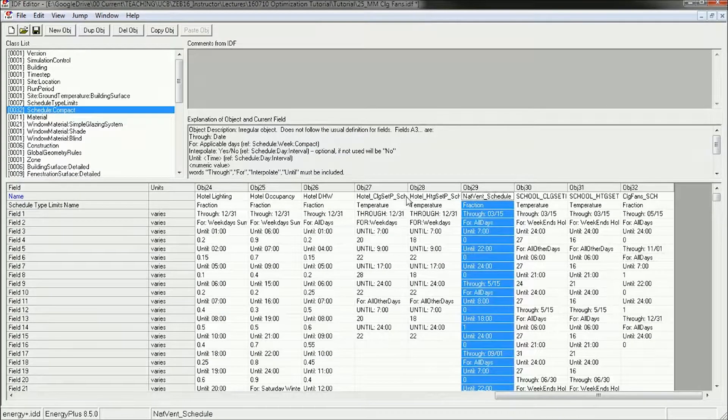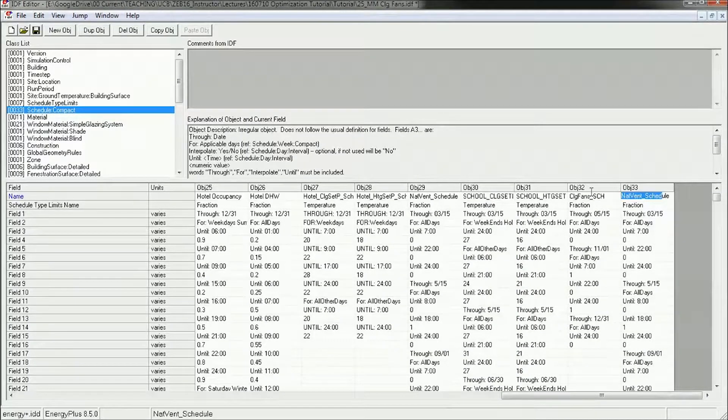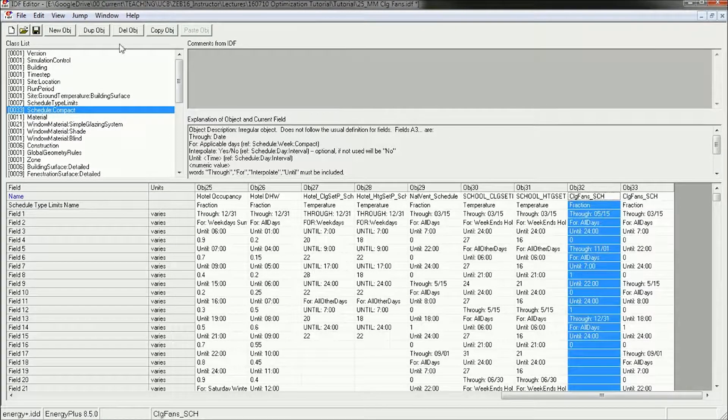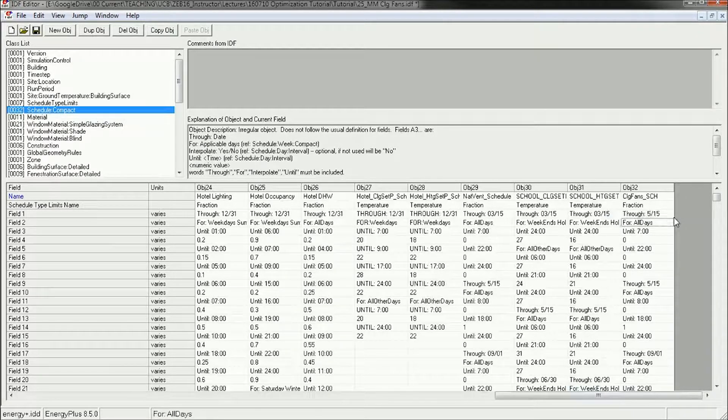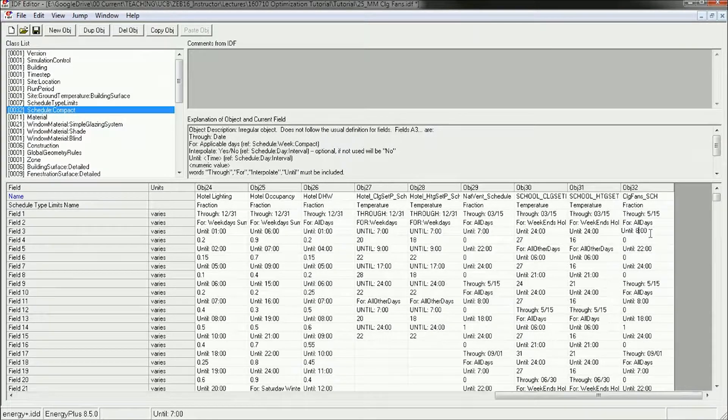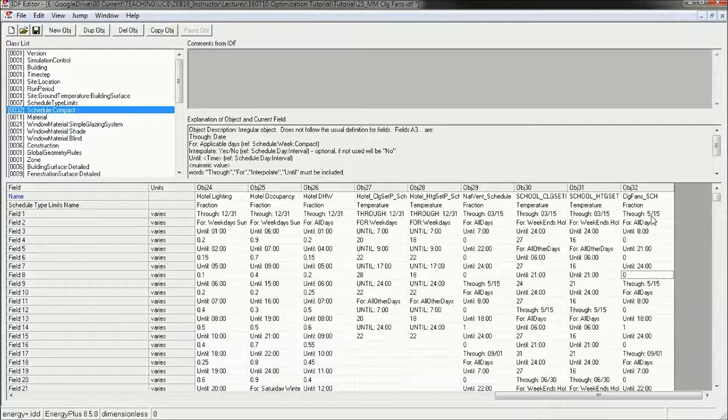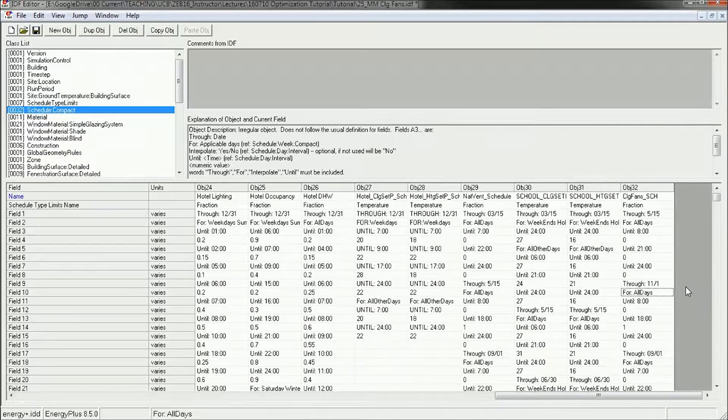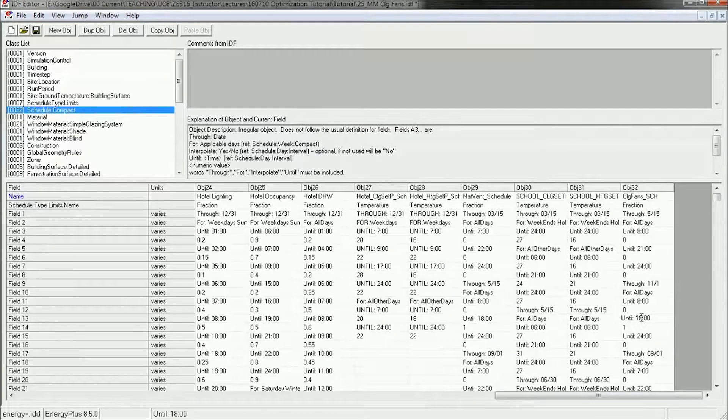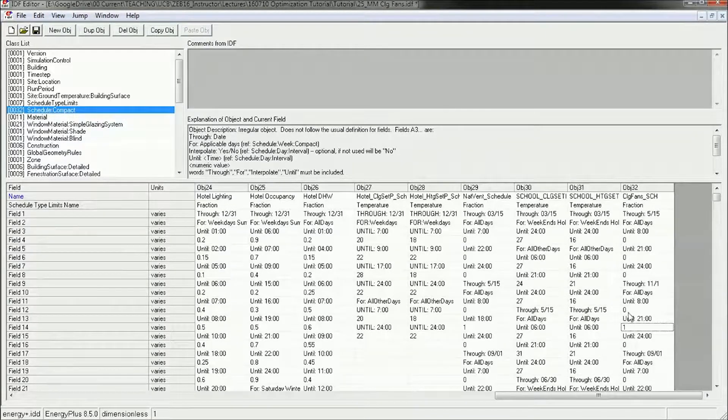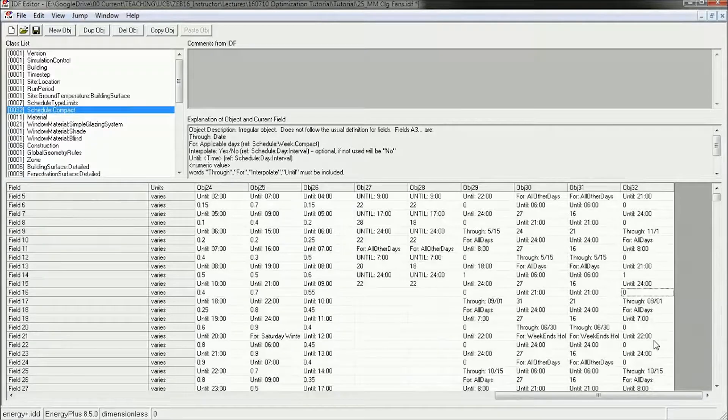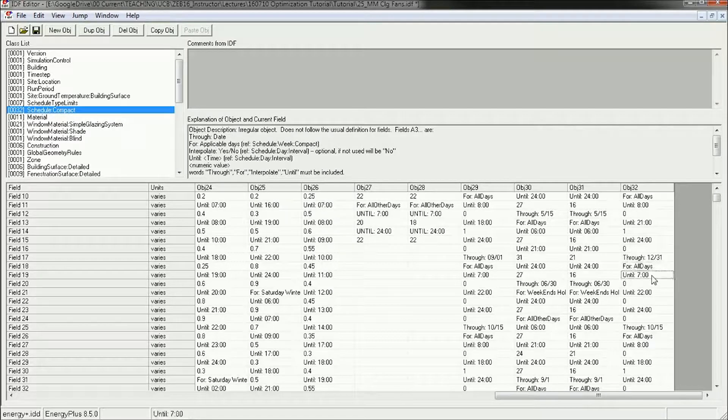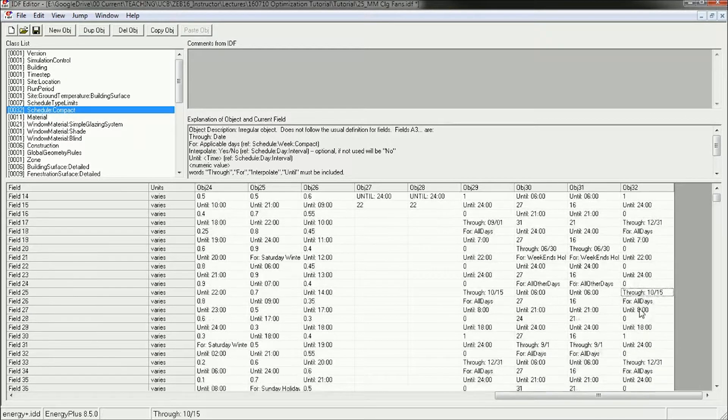Let's make... I'm going to use the natural ventilation schedule. So I'm going to call this the Ceiling Fans Schedule and delete this one. We'll start May 15th for all days from 8 a.m. until 9 p.m. From May 15th until November 1st, we want the fans on from 8 o'clock to 9 p.m., and then from November 1st to December 31st, we want them off.